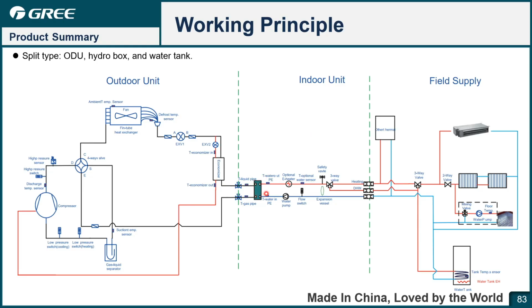For the indoor unit, the cold water will flow from here, flow to the flow switch. Okay, the water pump circulates in to get the heat from the refrigerant and then flow out. If the heat pump capacity is insufficient, it can use the optional heater to get the additional heat source. And this is a sensor, safety valve, three-way valve to control the flow direction.